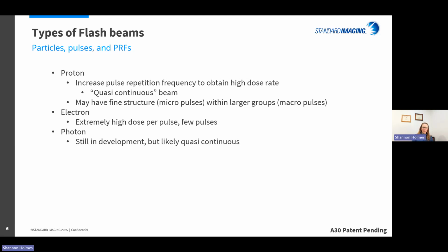So the type of particle, we can measure all of those with ion chambers. The type of particle isn't as big an issue. The way the pulses are generated and the pulse repetition frequencies, or PRFs, that's what really plays into your ion chamber response. So for protons, in order to get to flash dose rates, a lot of proton systems increase the pulse repetition frequency. It wasn't a major increase in the pulse height, but you're jamming those pulses all together into a short time frame, which generates what's often referred to as a quasi-continuous beam. Those pulses are so close together that the measurement systems really see that as an almost continuous beam.